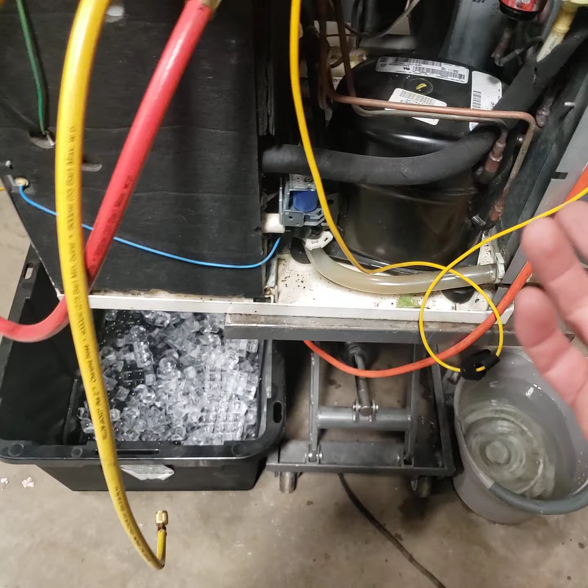They have enough freon. Same thing if you put your hand here and this guy is cold and sweating, as you see, that means there's enough freon. When you put your hand here, you see the air much warmer than if you put it here. Here is cooler. The compressor is working and there's enough freon in there. Okay, now if you put your hand here, it's cool, and this guy is like room temperature, while the unit should be calling for AC, and the compressor is running. You put your hand here, it's the same temperature here and there, and the fan is running. There's something wrong. Either the compressor has a problem or there's no freon.